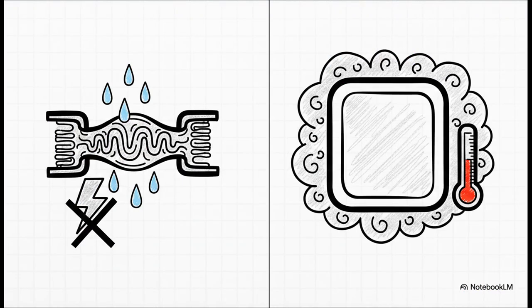As you can imagine, spinning massive metal rotors and pushing thousands of amps creates an absolutely astronomical amount of heat. And if we don't actively remove that heat, the entire plant will literally melt down. So to act as the lungs of the plant, engineers typically use two highly specialized cooling methods. First up is demineralized water, or demi-water. Because it's had all its minerals completely stripped out, it doesn't conduct electricity at all. That makes it perfect for flowing directly through the stator windings to carry heat away safely.